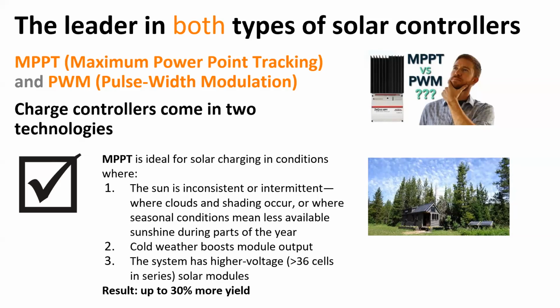MPPTs typically have the most benefit in colder climates. Cold temperatures cause the array to go closer to their open circuit voltage, in accordance with their temperature coefficient as stated on the module data sheets. As that happens, it creates a larger voltage barrier between the array and the battery, and you need an efficient conversion process to step down the voltage but actually boost the current on the output, so power is preserved.